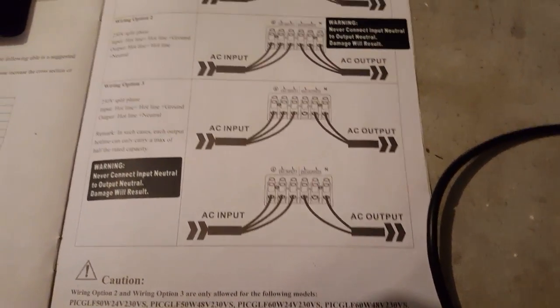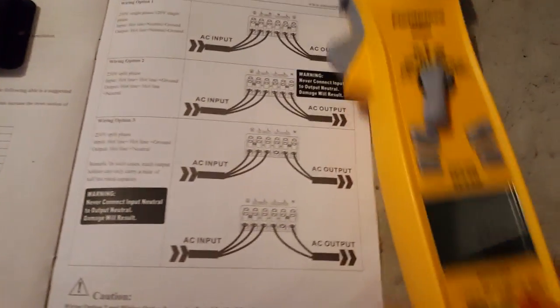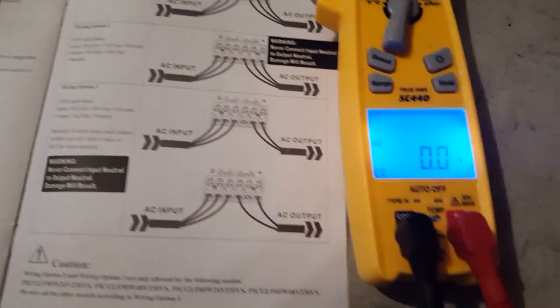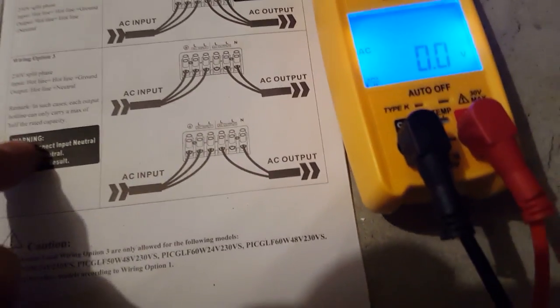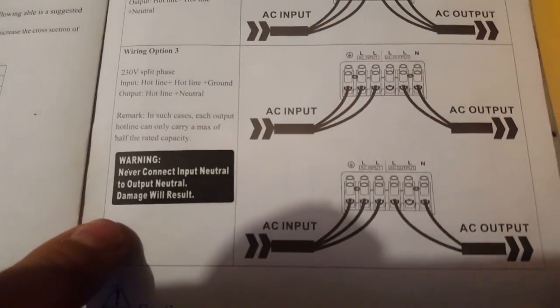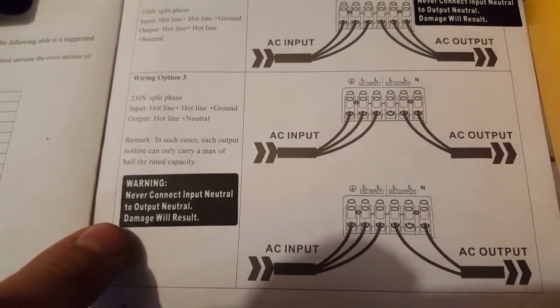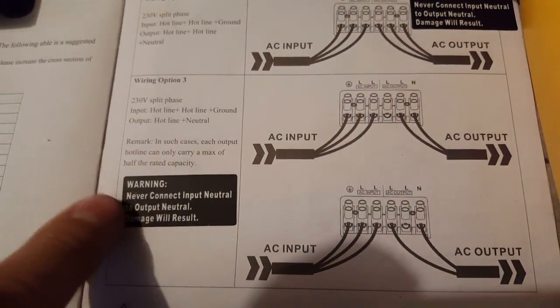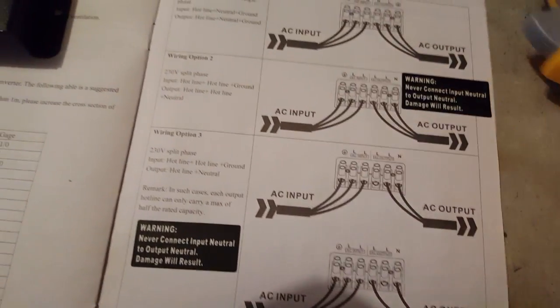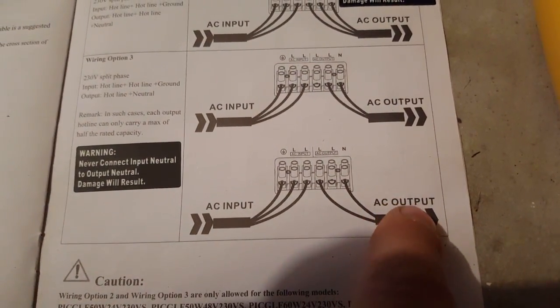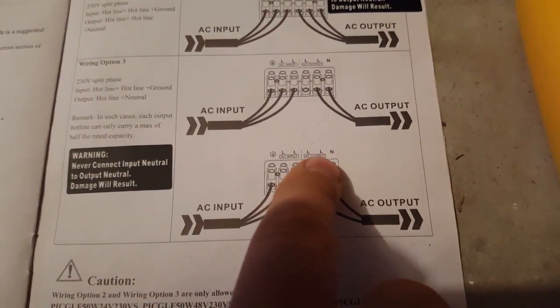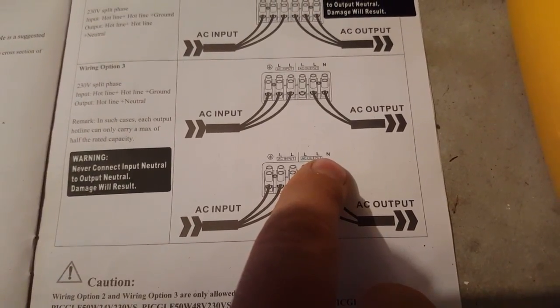Hello YouTube, this is Philip 20. Today I've got a couple comments that I wanted to clarify. This is the inverter's installation manual and you can see it says never connect the input neutral to the output neutral, damage will result. You can see here AC input and AC output, and it says N on the right and a ground symbol on the left.